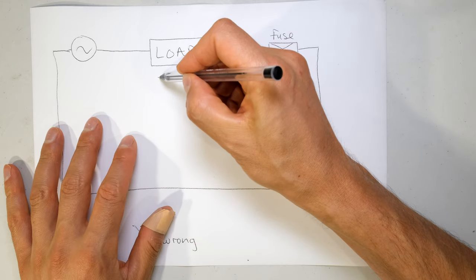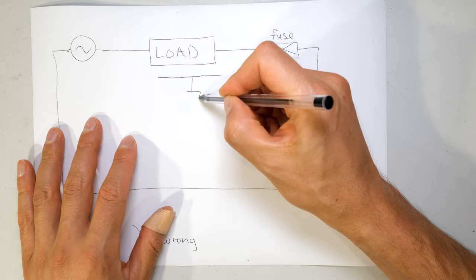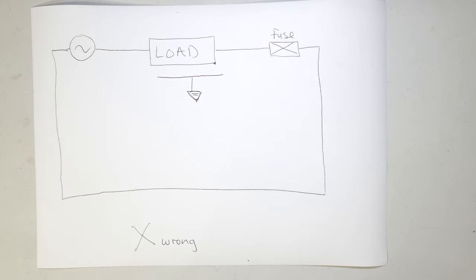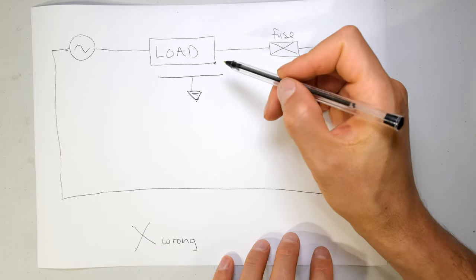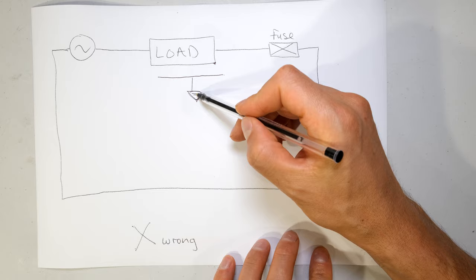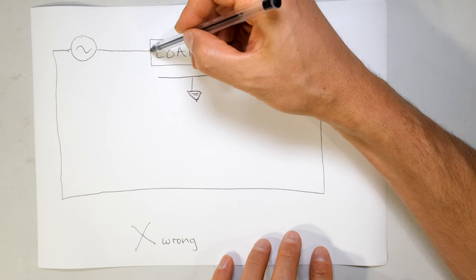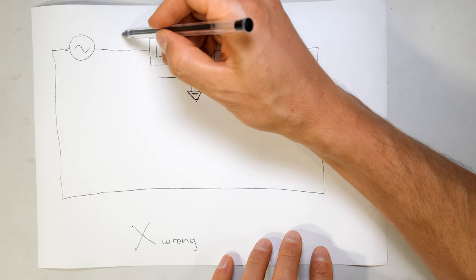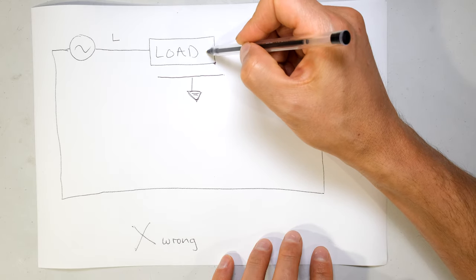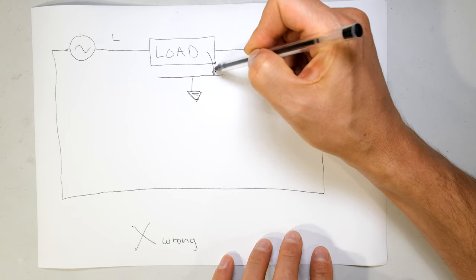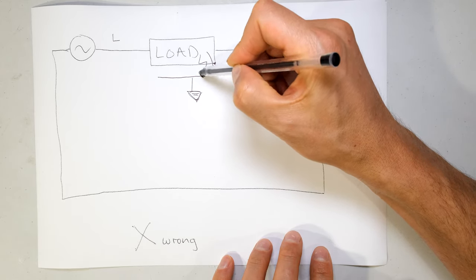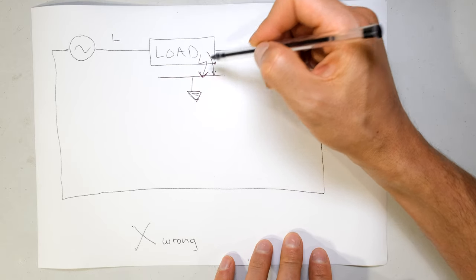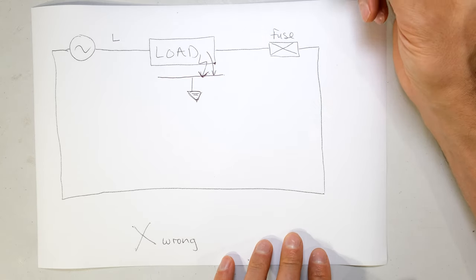So that means the chassis of that amplifier, or maybe it's your heater, maybe it's your oven, maybe it's a light fitting, is supposed to be connected to earth. Now what happens if there's a fault inside this load - there's your live wire and it is shorted to earth. So you're getting an earth fault like that, a live-to-earth connection.